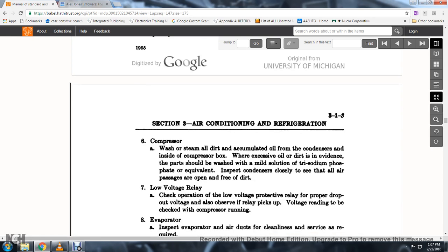6. Compressor. When the compressor is washed and steamed, remove all dirt and accumulated oil from the condensers inside the compressor box. When excess oil and dirt is in evidence, the parts should be washed with a mild solution of tri-sodium phosphate or equivalent.